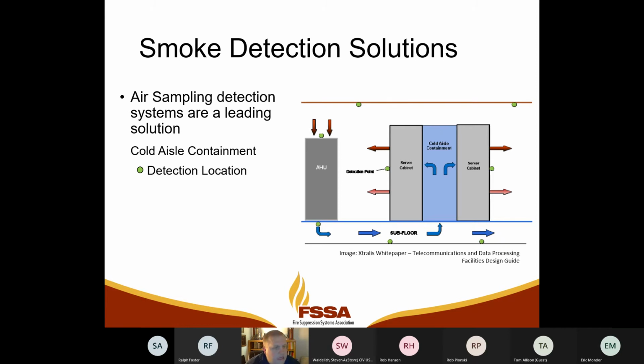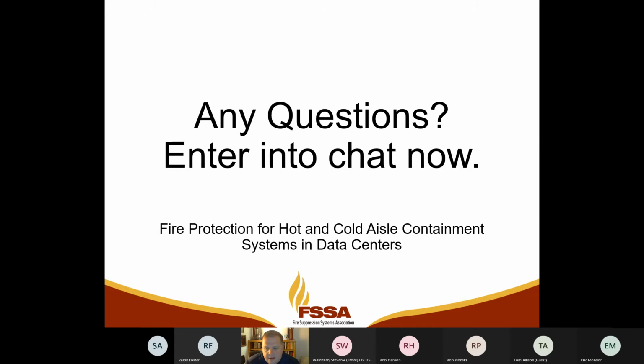Even though the code says if this is a contained space and you've got gas, you need to have detection, piping, nozzles, all those things, this is generally a bad spot to put detection because it's just dead air. You're not going to blow smoke by it ever, and it's just a waste of your money. So a couple hints there. That's my presentation, guys. It was a lot, and also very specific about data centers. Anything else that came to mind that I can answer?